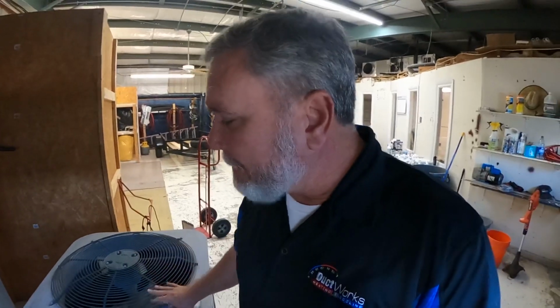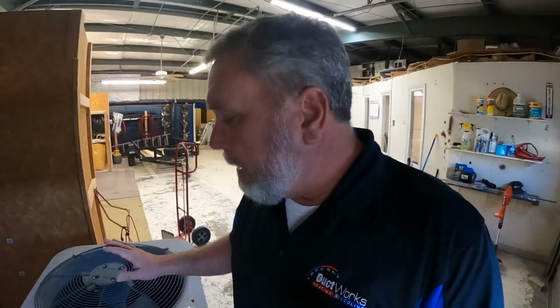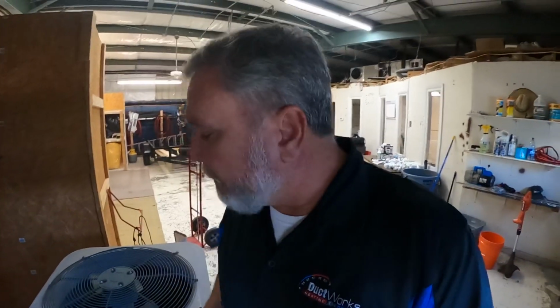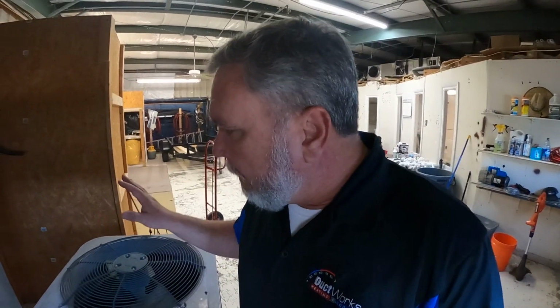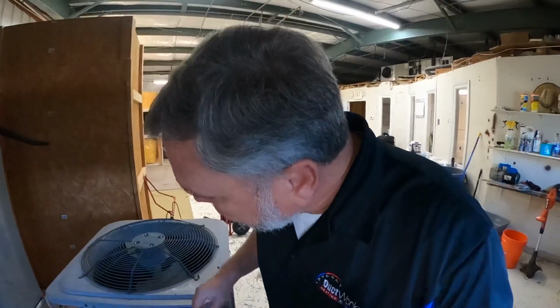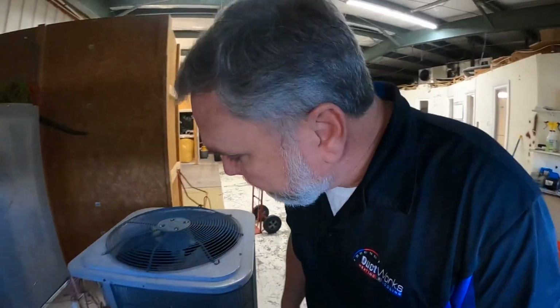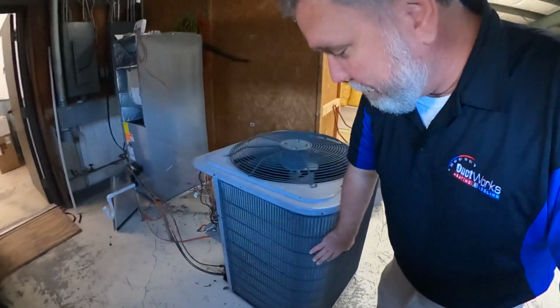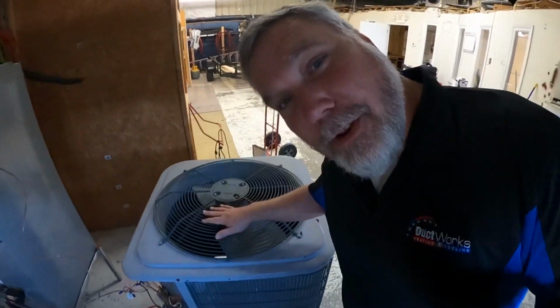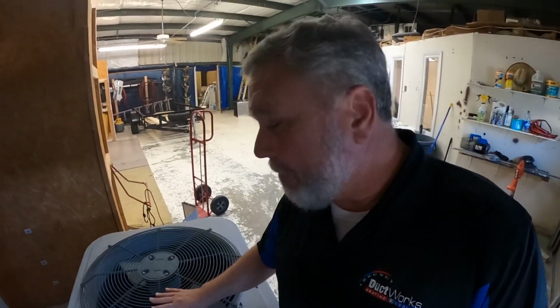First of all, we have a system here that we have set up in our warehouse location that we practice on. We let the guys practice troubleshooting on the system, especially guys who are coming up, who are kind of green in our industry, wanting to learn more about the service side. But a few things that we do. First of all, we clean these outdoor coils. We make sure all this is flush, with no dust, no debris in there. We go through the inside of the unit, especially if you're in a very heavy foliage area with leaves and sticks and all kinds of mess. We get all that cleaned out because it can build up in there.